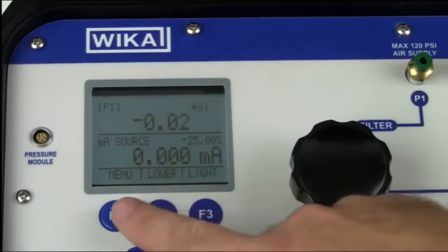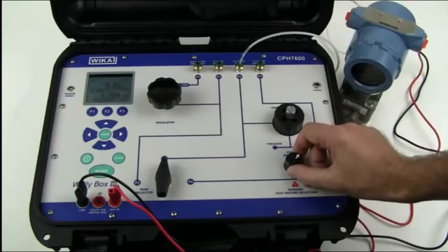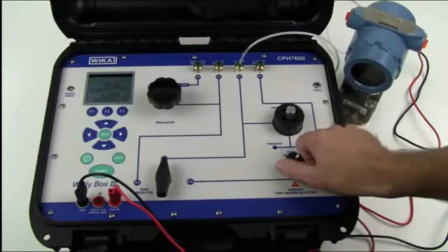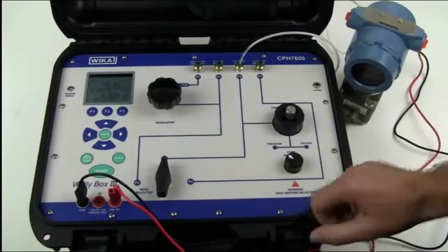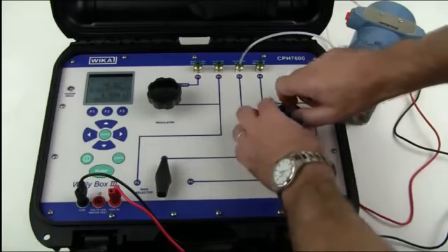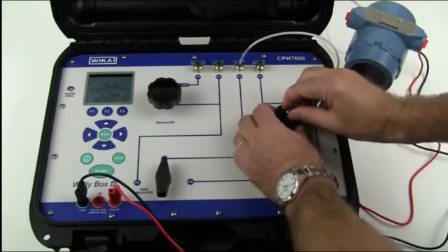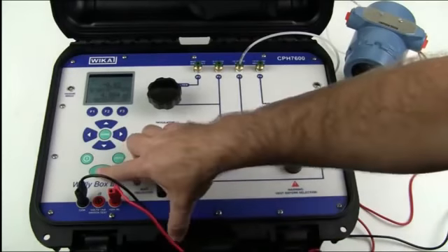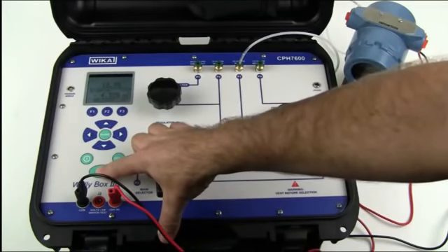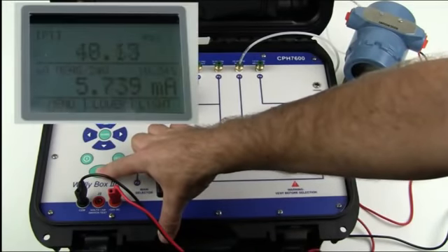We now need to make sure that the main selector is on position P3 to use the internal pump. The pump selector, in this case we want to go to 300 psi. We change it from vacuum to pressure. If we are happy with the 0, we can then go ahead and close the vent. We will then go ahead with the pump and take up the pressure. You will see the pressure increasing at the top half of the display, and in the bottom half of the display you will see the corresponding 4 to 20 milliamps coming out of the pressure transducer. The pump has already been preset to stop at 300 psi.